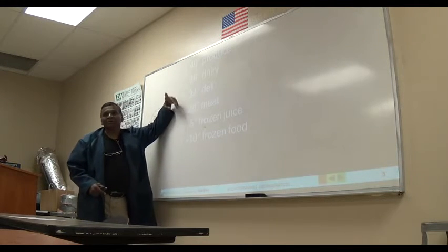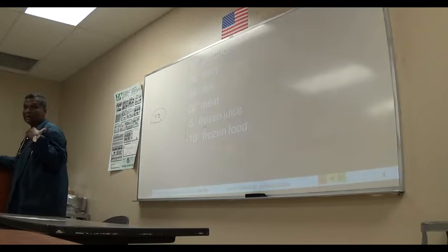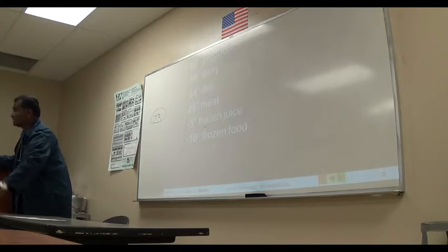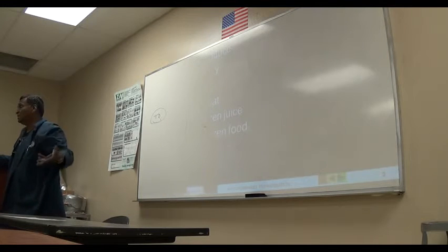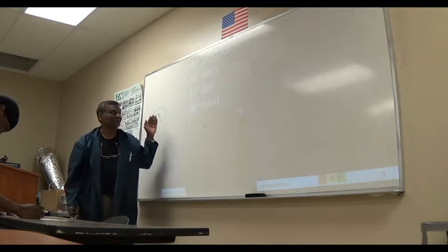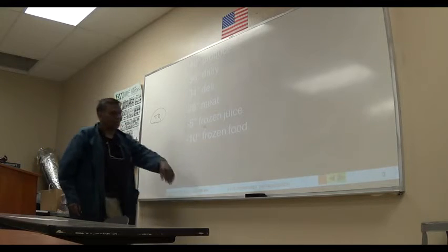Typically these are 10 degrees TD to 15 degrees. Now the manufacturer of that equipment will let you know what temperature difference to specify. Right on the condenser unit there's going to be a data plate, and it says design conditions 10 degrees TD, or they will give you temperatures in and out, and that will let you determine it. If it's not written, just go on the assumption that it's between 10 degrees and 15 degrees, because more often than not it does not go to 20 degrees or even 25 degrees like the air conditioner.